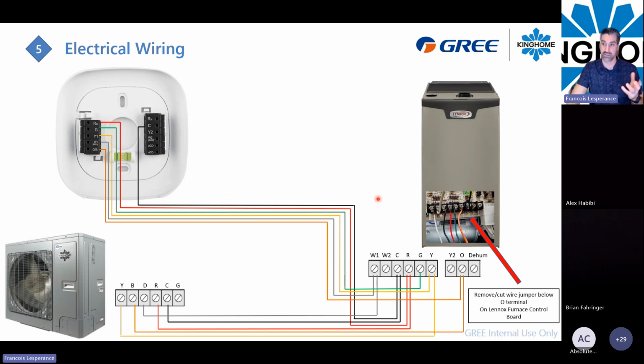Why it's called O or B depends on what kind of heat pump you're using. With unitary heat pumps, back a couple of years ago, every reversing valve was active in cooling, so we were using the O terminal. This is why some labeling can be O. But today, for the Kinghome model, every kind of unit from Kinghome has the reversing valve active in heating mode, so we will use the B terminal.